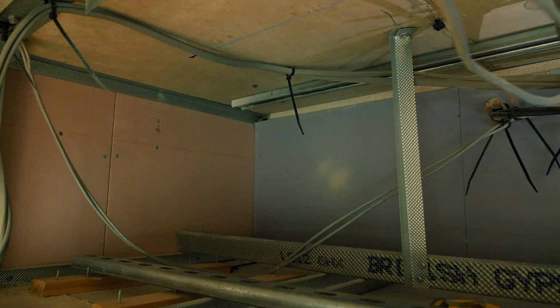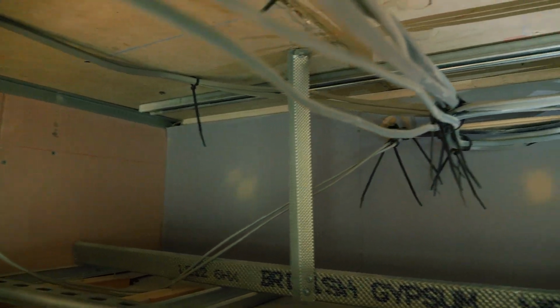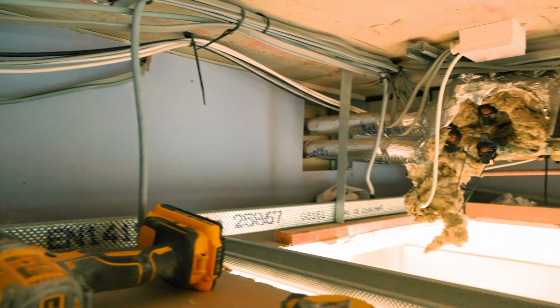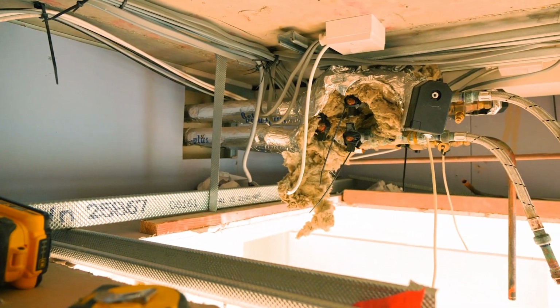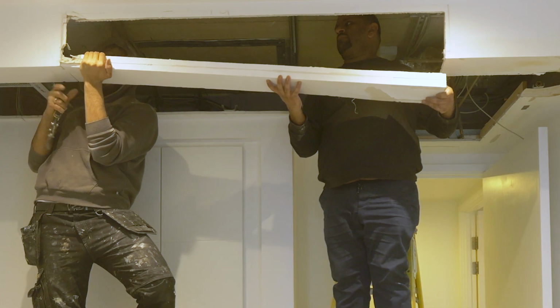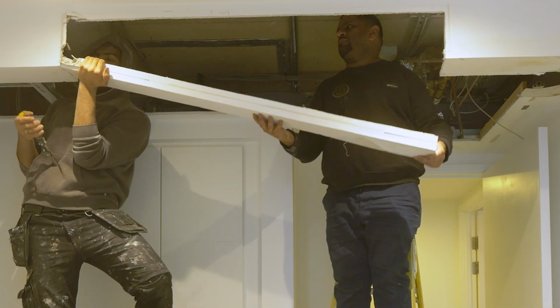As you can imagine, installing a fan coil unit with a much larger footprint, not every bulkhead will allow for this. We were quite fortunate when we carried out the survey. I had a quick look. I could see no soil pipes in here. I could see some T&E cables, some lighting running. We did our measurements to ensure that the new fan coil unit would fit. But as you can see, it was still very tricky. We had to remove a lot of the face of the grill to actually get the unit in.